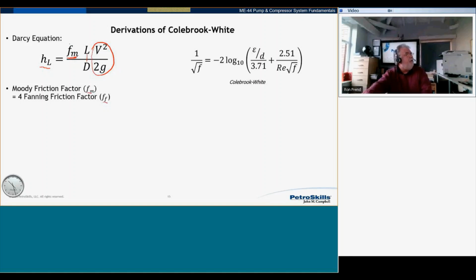But how do I figure out this? Because length of the pipe, no problem. Diameter of the pipe, no problem. Velocity of the liquid flowing through the pipe, no problem. I can work that out really easily. This is the difficult thing. This is where I'm going to spend a little bit of time. Now, what we could do is use Colebrook-White. We've got this formula here. So I can make a guess at the number for f, plug it into this calculation, and see if that side equals that side. It's iterative. You have to do it a few times. Usually 3 is plenty. But there are other ways of doing this.